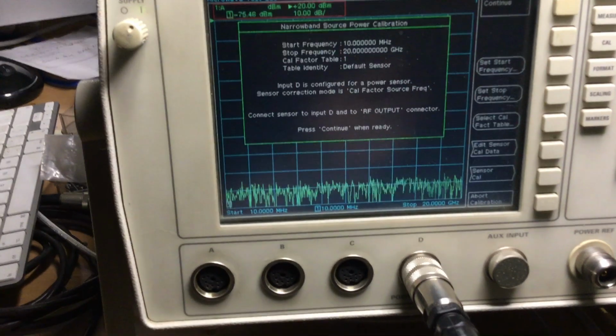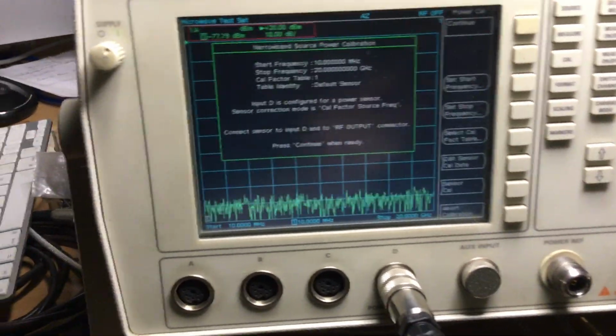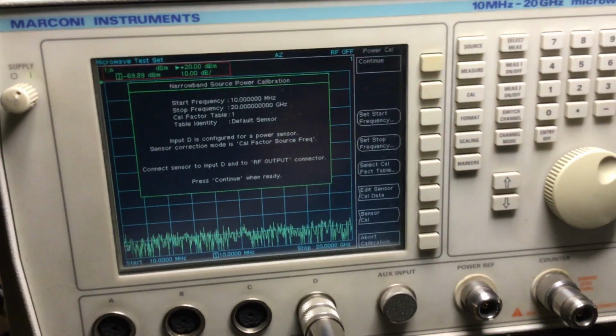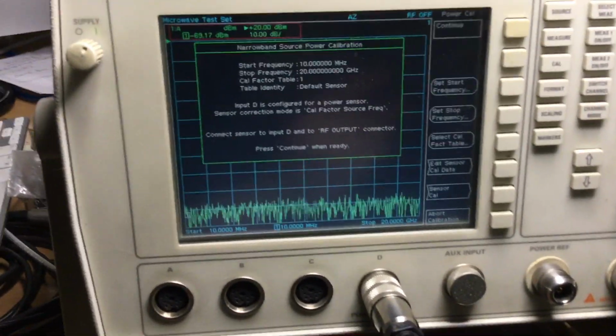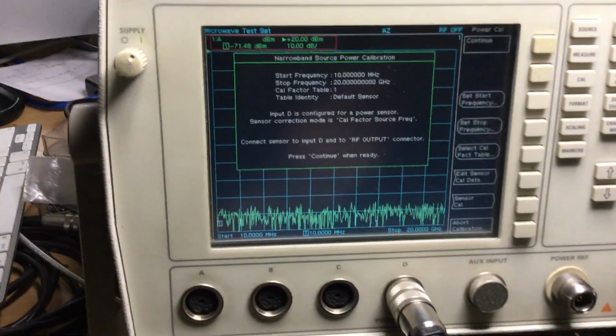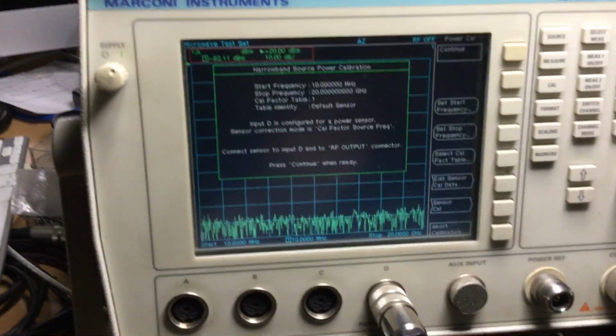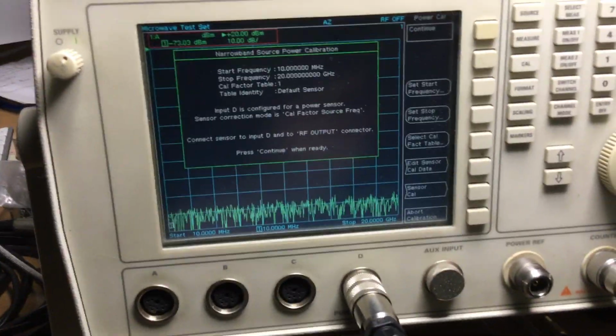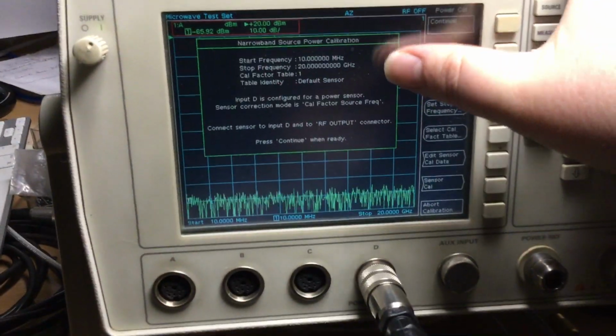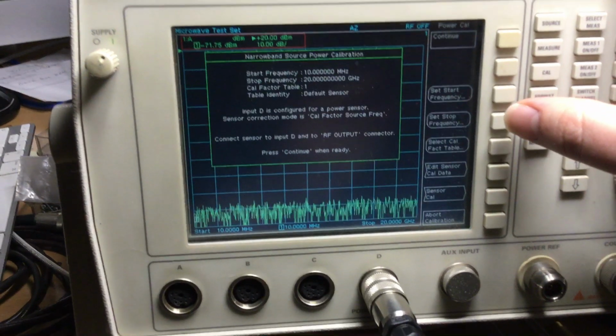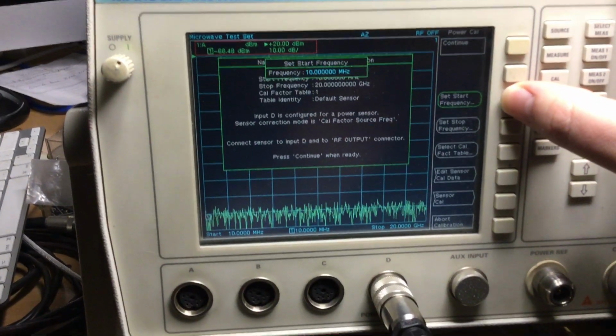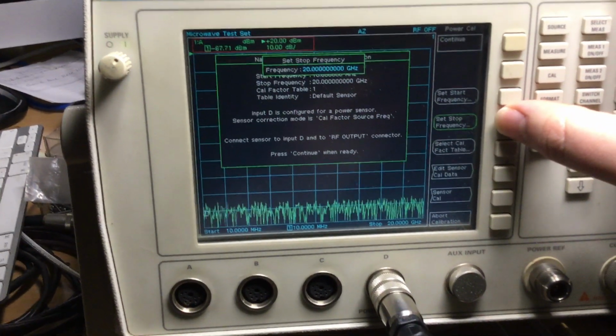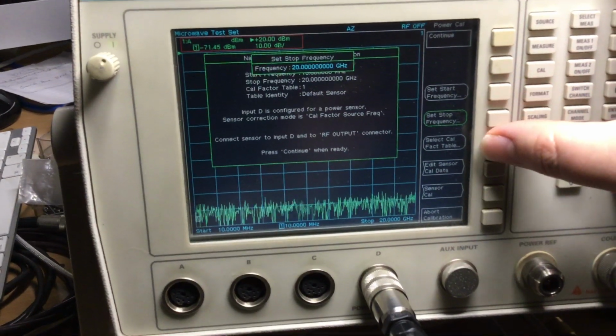Right, so I've got various passwords here which I've had to refer to, because there are level 1 and level 2 passwords depending on which application or which calibration you're going into. It will entirely depend on what password you need to use. So these are the frequencies that we do the calibration over. You can set a start frequency and a stop frequency. You can do narrowband as you like, really.